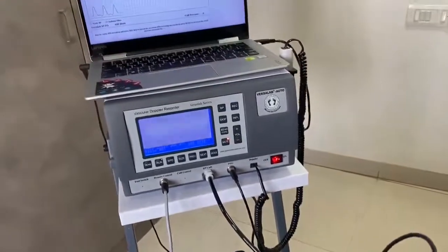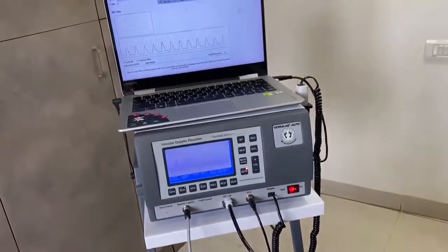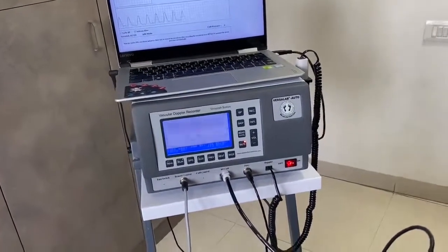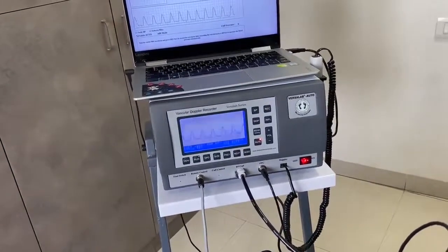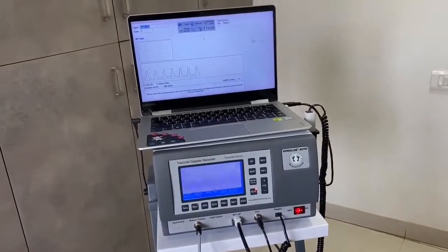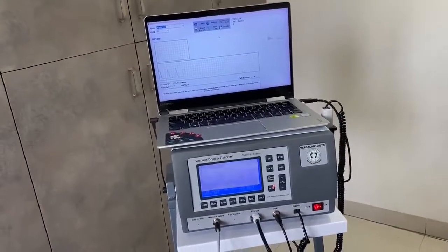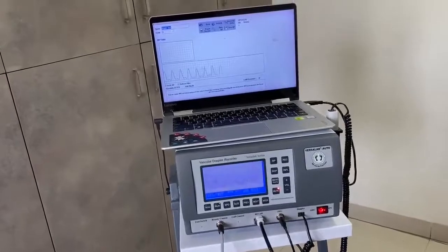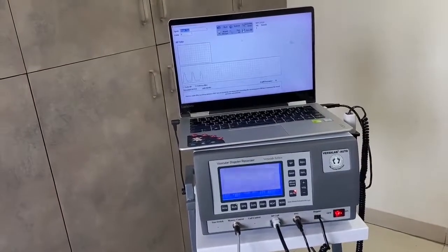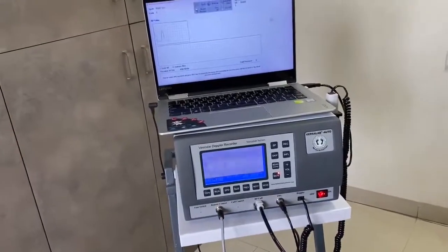And you can see on the waveform, like a pulse oximeter, you have a pulse waveform on the screen. You will also get a small beep sound. It is not like Doppler, but we are actually sensing every beat. For a good normal recording and also good BP measurement, always try to have a waveform which can produce this kind of sound. Then it will be accurate. If there is any vasoconstriction, then you have to rub the finger and then you can measure. Now I am recording it. See, it is recorded on the top.